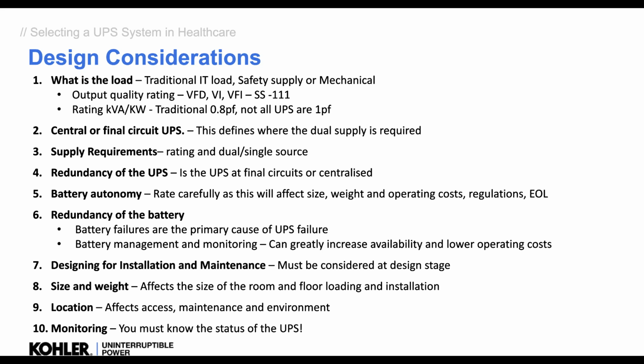Batteries are the primary cause of UPS failures, typically because they're not looked after. People don't understand the state of them, and they don't test them. So we need to put some redundancy in that battery. That's the best way of doing it, alongside monitoring and management of the battery. It's often not considered when we're putting in a UPS. People don't talk about the battery, they talk about redundancy in the UPS and forget the battery.